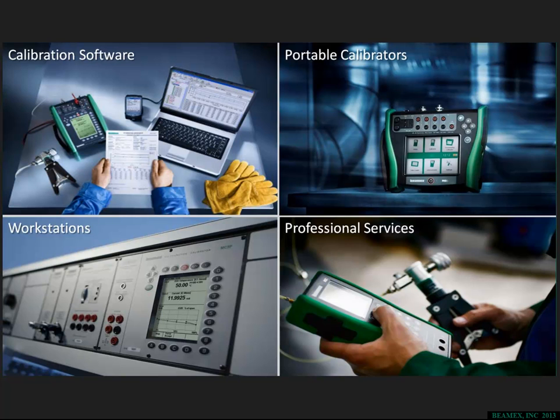Today you may be using just pen and paper or spreadsheets, possibly even a database, to determine what instruments require regular calibration to ensure they're performing and measuring to any specified tolerances. Especially with increasing regulations from agencies in the U.S. like the FDA and EPA, having a solid system in place is vital. Calibration software is a tool that you can use to support and guide your calibration activities, provide documentation, and traceability as well.